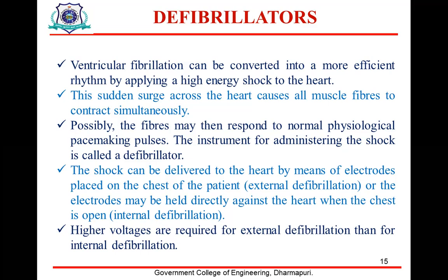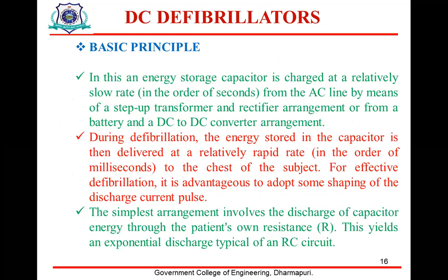The shock can be delivered to the heart by means of electrodes placed on the chest of the patient. This is external defibrillation. Or the electrodes may be held directly against the heart when the chest is open. This is internal defibrillation. Higher voltages are required for external defibrillation than for internal defibrillation. For a DC defibrillator, what is the basic principle? An energy storage capacitor is charged at a relatively slow rate, in the order of seconds, from the AC line by means of a step-up transformer and rectifier arrangement, or from a battery and a DC to DC converter arrangement. During defibrillation, the energy stored in the capacitor is then delivered at a relatively rapid rate, in the order of milliseconds, to the chest of the subject.